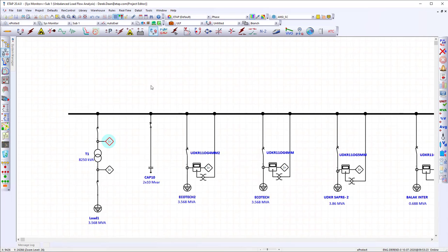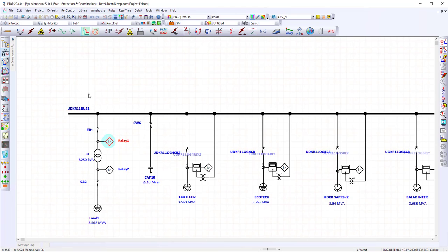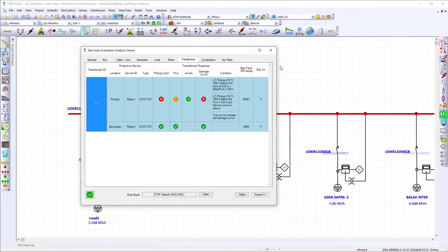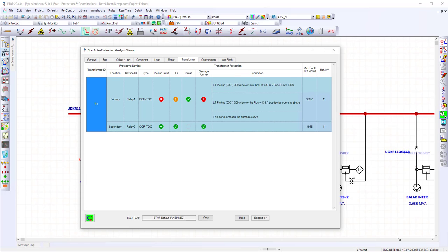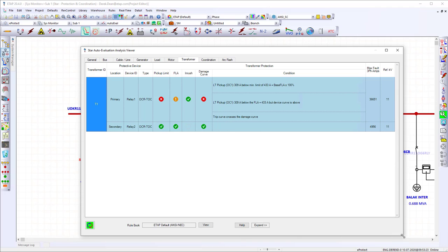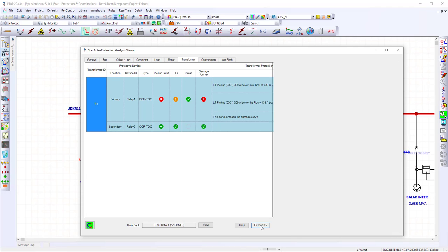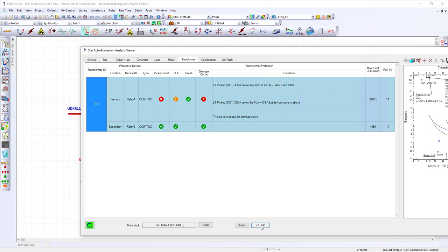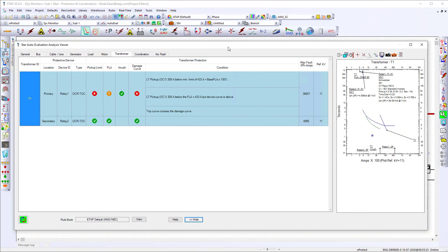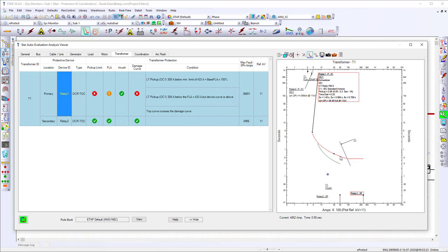Now we can do a protection study with these settings and use Star Auto to automatically evaluate the protection settings. Star Auto tells me that I have errors based on the long time pickup value, which is below the minimum limit of 433 amps, which is based off of base FLA times 100%. These guidelines are set in the Star Auto rulebook. I can adjust the settings directly from the TCC view within Star Auto.